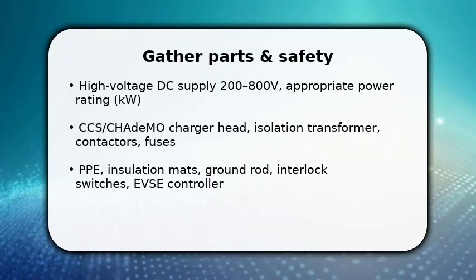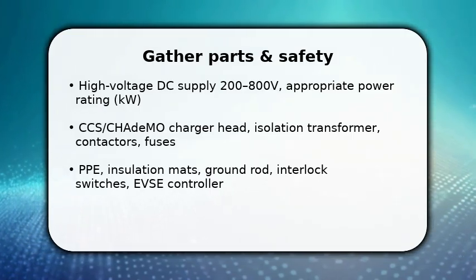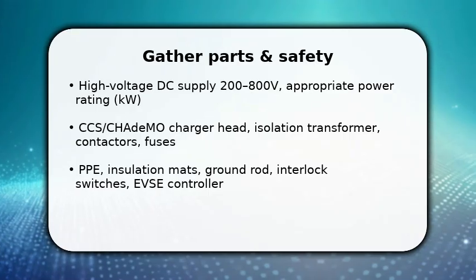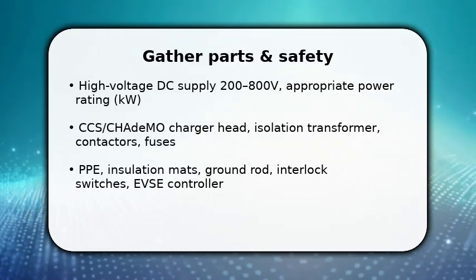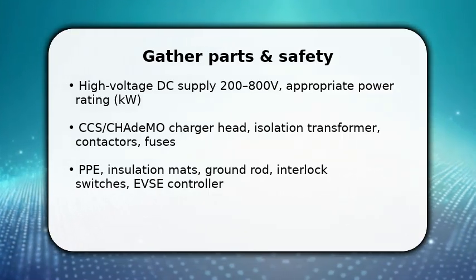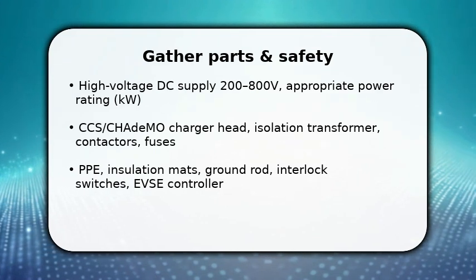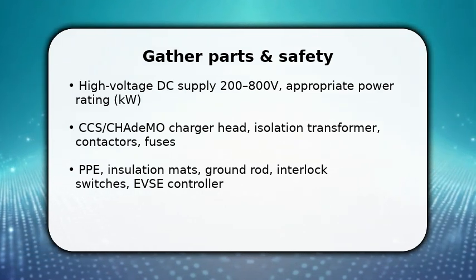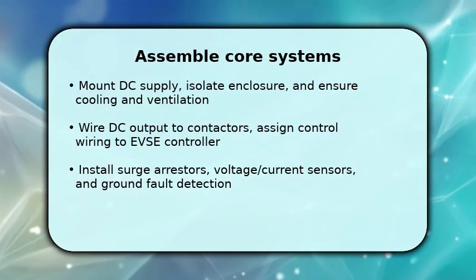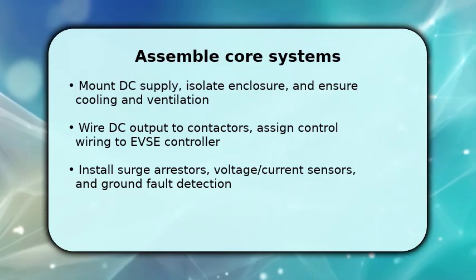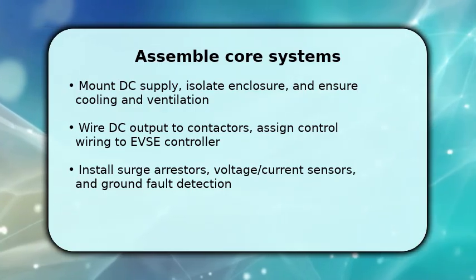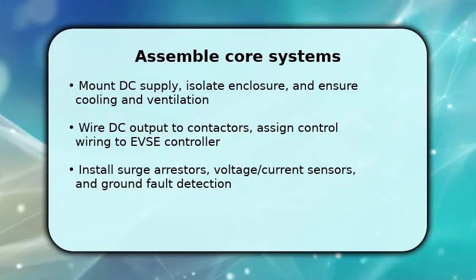Order an EVSE controller that supports CCS or CHAdeMO and can handle PLC communications. Once parts arrive, lay them out logically and label every component so wiring and tests stay organized and traceable. Begin by mounting the DC power module inside an IP-rated enclosure with adequate cooling. Make sure clearances meet vendor specs.